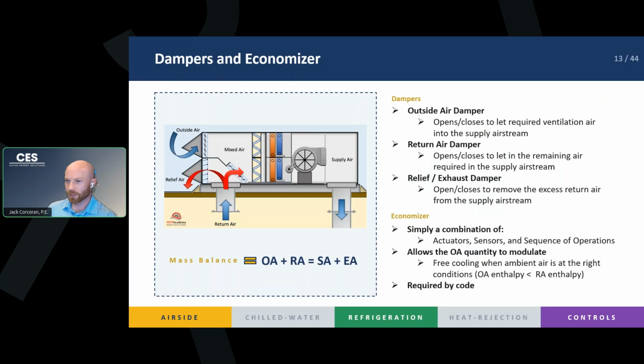So the first component, our dampers and our economizers, right? So this is all about mass balance, right? Our airflow balance. So you have a fixed amount of supply air that's going out of our unit. So you need to have air coming into the unit in order for that to work. So if you look at our mass balance equation here, our outside air plus the return air, those are the two sources of air coming into the unit, and that's going to equal the air going out, which is the supply air and the relief or exhaust air, right? And so in order to have an equally pressurized building, that equation has to be true. The air coming in has to equal the air coming out.